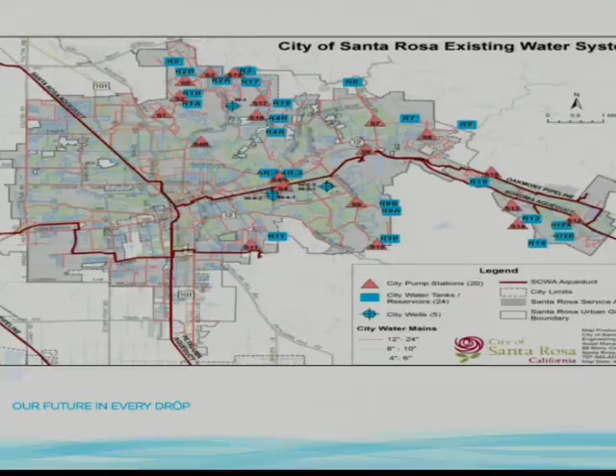We have about 18 major pressure zones, and off those pressure zones it pumps up to a tank, bleeds back down, and when pressure gets too high at the lower part of the elevation of that zone, it has to be regulated to make it sustainable for the residents who live there. It's somewhat of a complex area — I've been to presentations where in the valley, for example, people talk about 2 pressure zones for a city this size, so it gets a little involved.